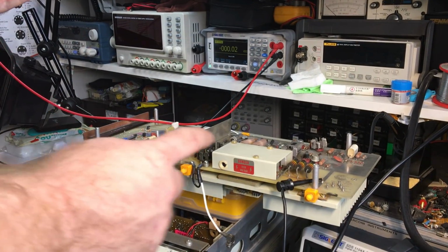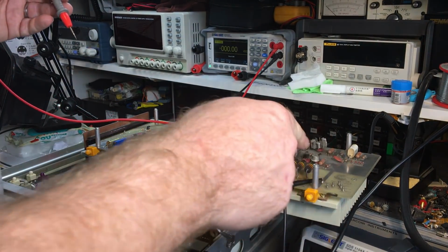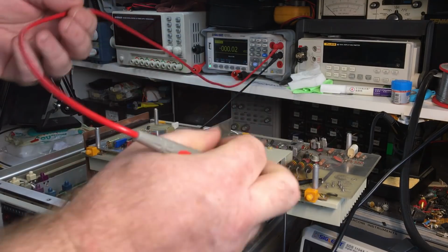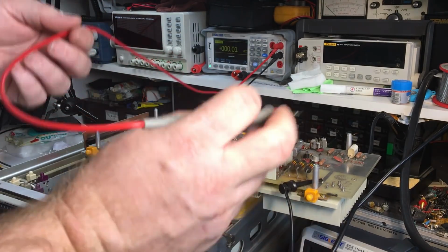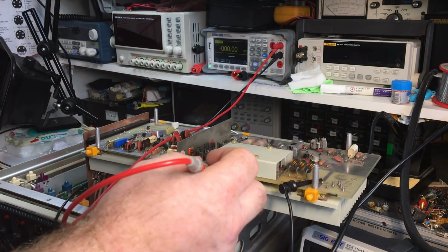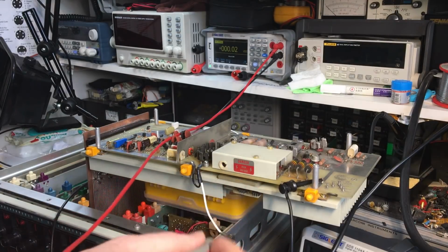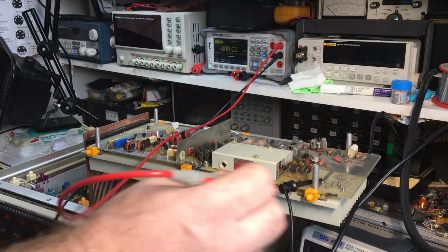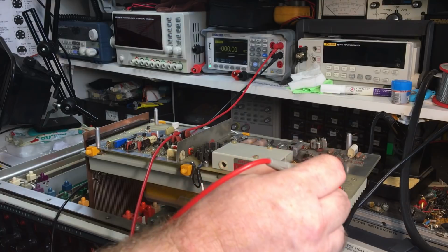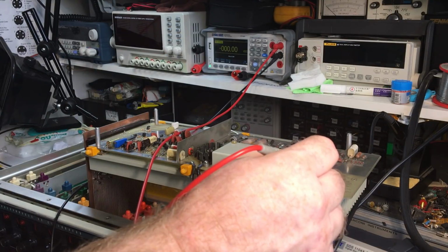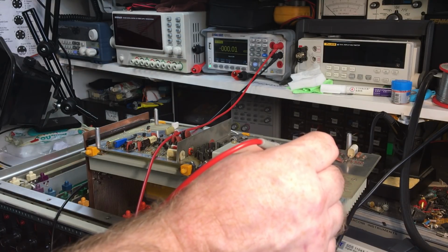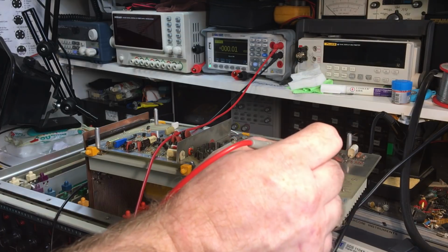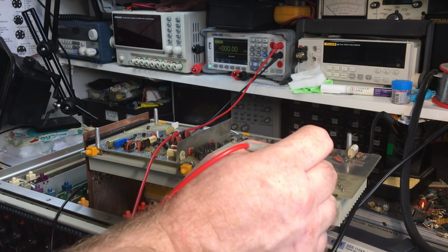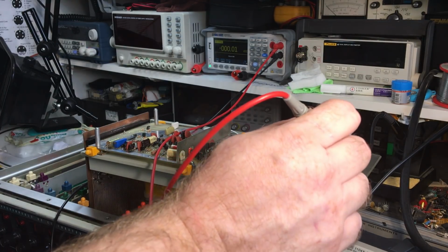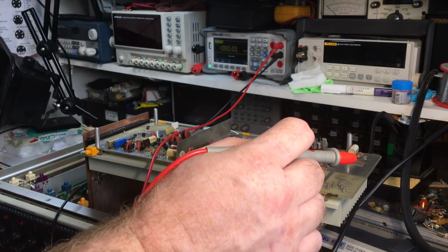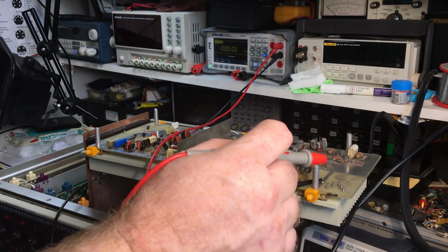Okay, so now I've got the test point hooked up to TP6, which is the low range. Well, 0 volt, well, the negative on the meter. I really should find out what terminology I should be using for that. I don't know, the black wire. Alright. So I've got a measure on TP1 for minus 190 volts. It's got to be between minus 180 and minus 200.